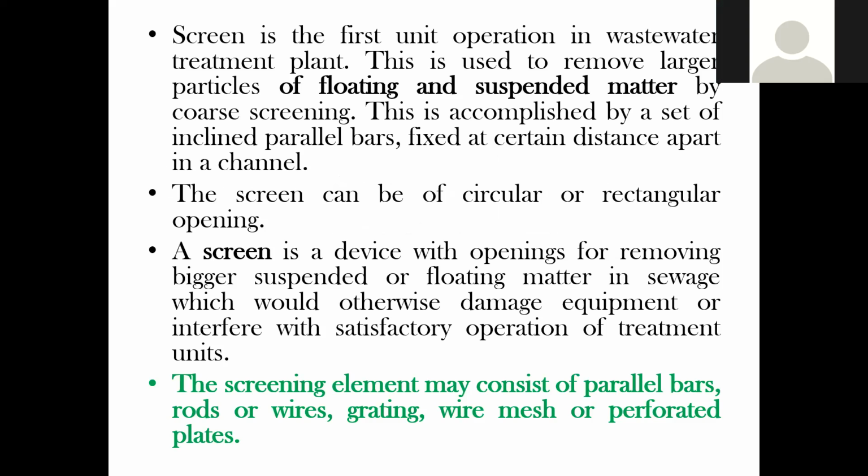I'm going to show you the figure through which you will understand better. The bars are fixed at a certain distance apart in a channel. The screen can be circular or rectangular in opening. A screen is a device with openings for removing bigger suspended or floating matter in sewage, which would otherwise damage equipment or interfere with satisfactory operation of treatment units. The screening element may consist of parallel bars, rods or wires, gratings, wire mesh, or perforated plates.